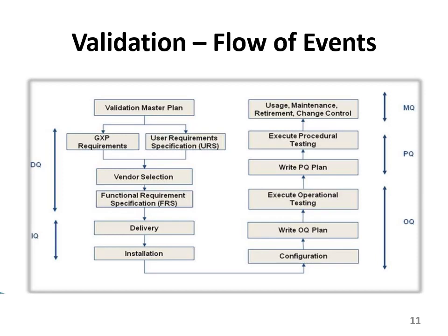So after installation, OQ, that is operational qualification, is where you start the operation on your machine. After installation, you configure it so that everything is okay and you are settled with the machine or equipment, and then write the OQ plan, how to operate it. Write it down. It will not only be easy, but it will be better for the machine and for yourself and for the process, all the things.